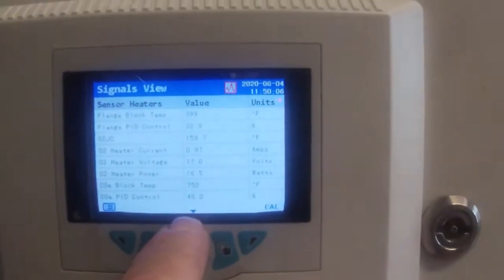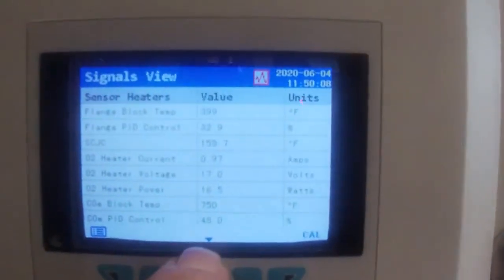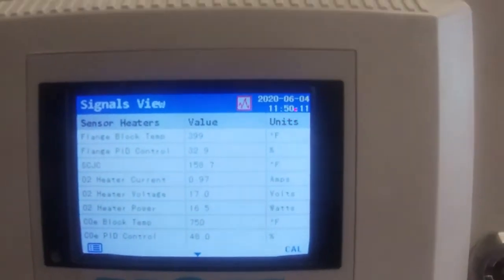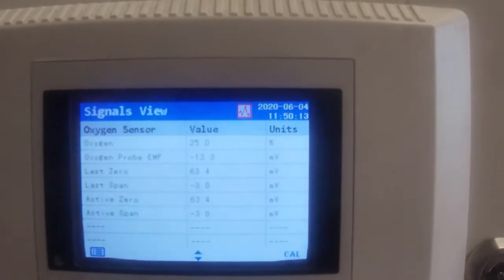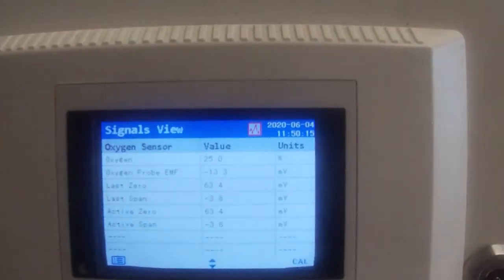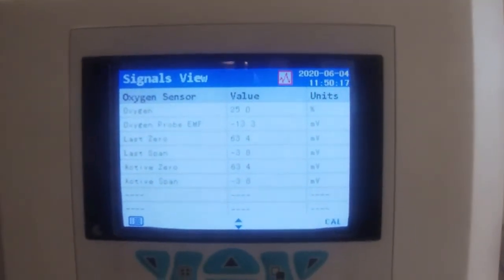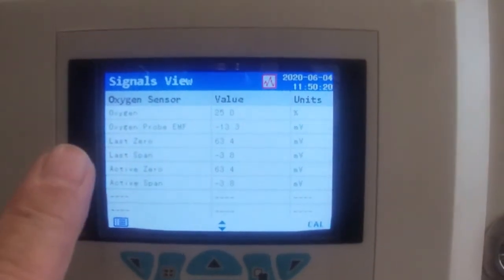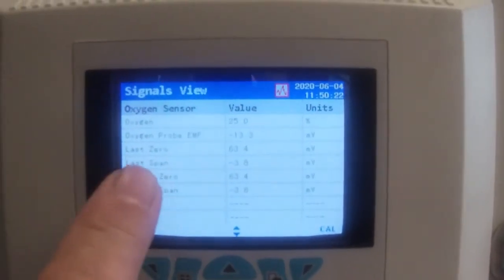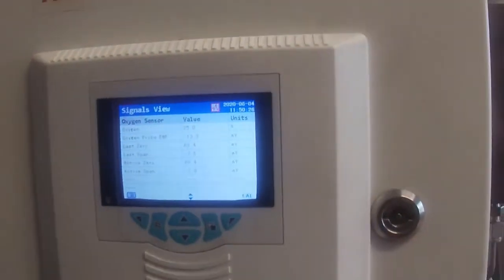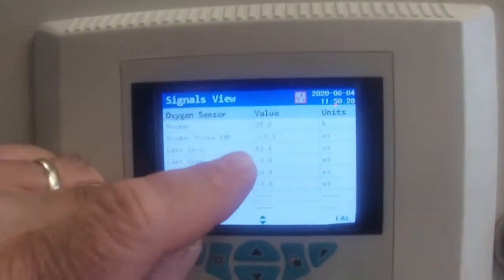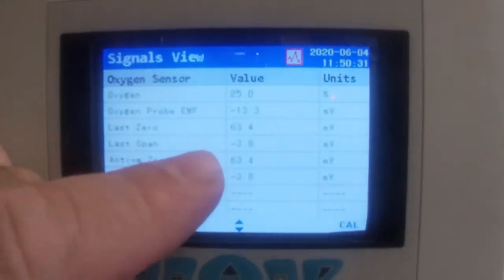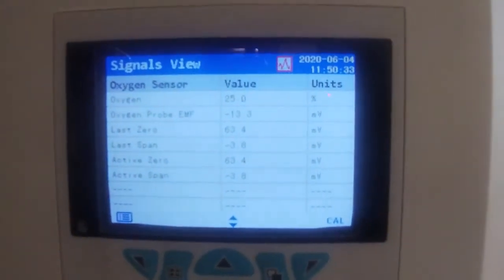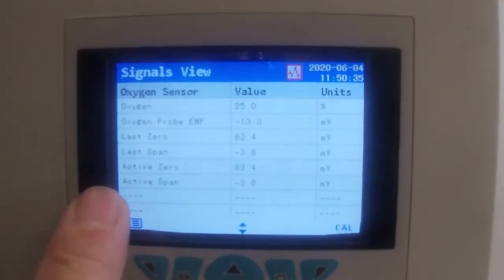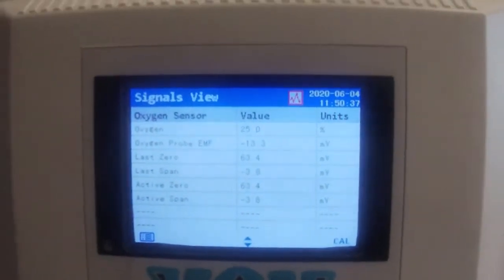You'll notice there's a down arrow there, which means, looking at this, there's more pages of information, and it's a lot. So on the next page, and you see now I got a down and an up arrow, which means there's more pages after this, or I could go back to the original page. It's telling me the oxygen right now. It's telling me the EMF coming off of the probe itself. Okay. And then what the last zero and span values were in millivolts for calibrating it, and then what the active zero and span, and they're exactly the same.